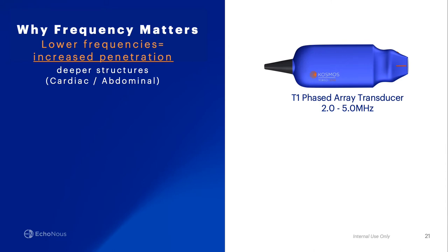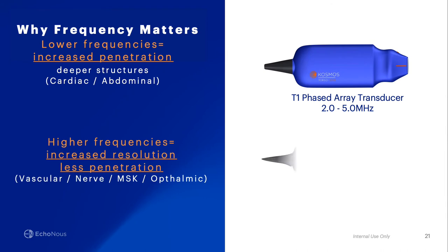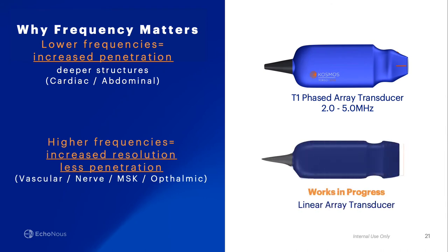Lower frequencies offer enhanced penetration capabilities to visualize deeper structures and are employed when visualizing cardiac and abdominal structures. Higher frequencies offer increased resolving capabilities, but sacrifice the penetration advantages compared to lower frequencies. Higher frequency technology is generally used to visualize superficial structures when penetration is less of a concern.